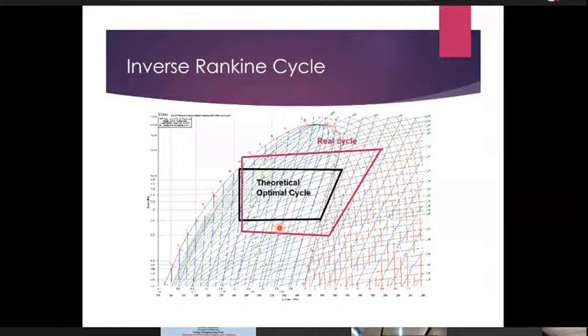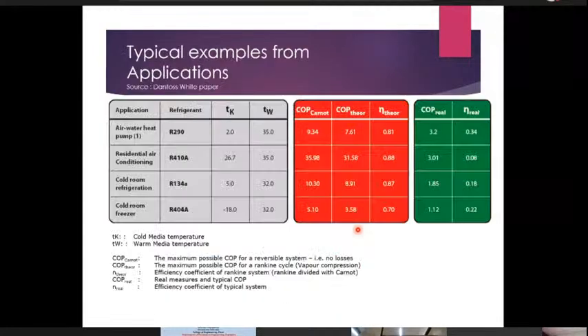Now we go to the next slide, and this is a slide which gives some examples on where we are today and the opportunity that we have going forward. So if you look at an air water heat pump using R290 as a refrigerant, with an air temperature of 2 and a water temperature of 35, so 35 is being used to keep the air warm. We will have a COP of the inverse Carnot cycle, then a COP theoretical, which is of the ideal inverse Rankine cycle, and then there is a factor. So what is the theoretical COP efficiency that we can get? And then we have the real system.